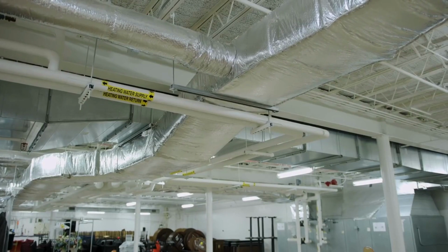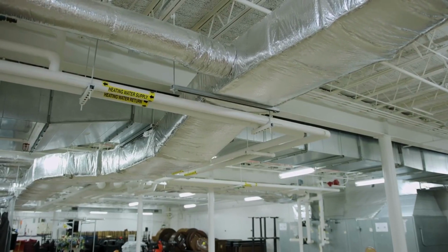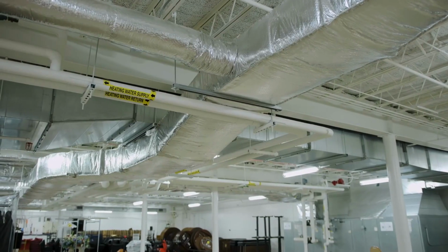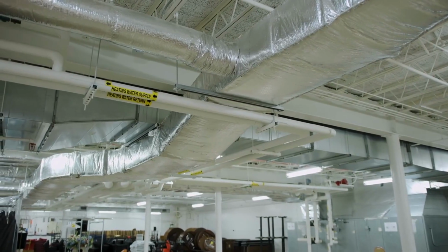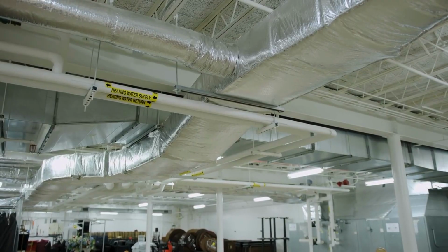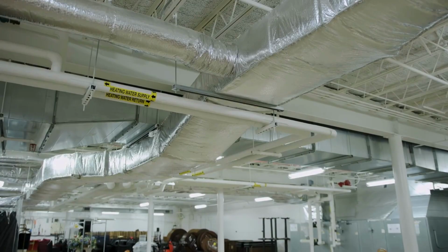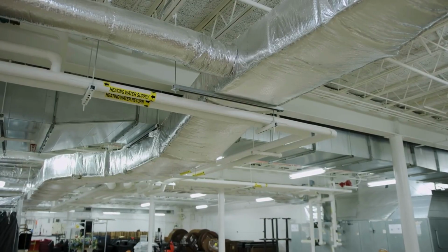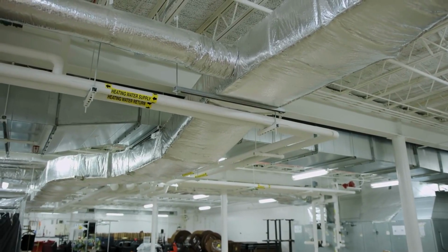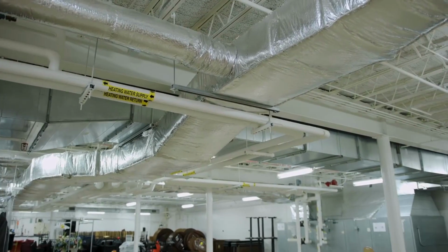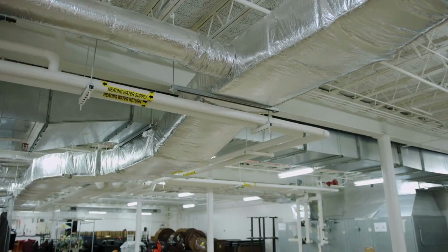6.2.2. Ductwork and shafts. 1. To maximize floor space for instruction, the SCA prefers roof-mounted DX heat pump units. The ductwork from these units must have multiple supply and return risers within multiple 2-hour rated shafts. The horizontal distribution ductwork should be headered in the space above the top floor's suspended ceiling to allow for smaller ductwork on lower floors and shallower slab-to-slab heights.